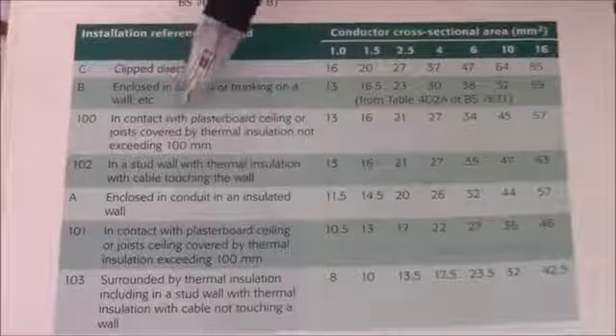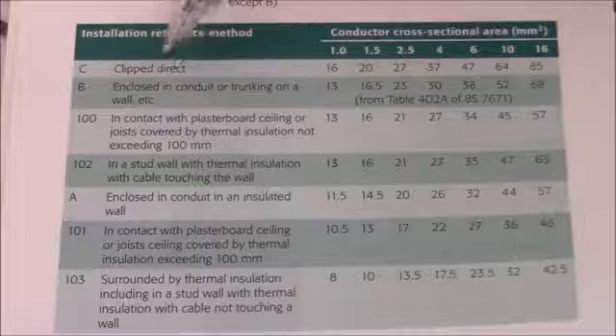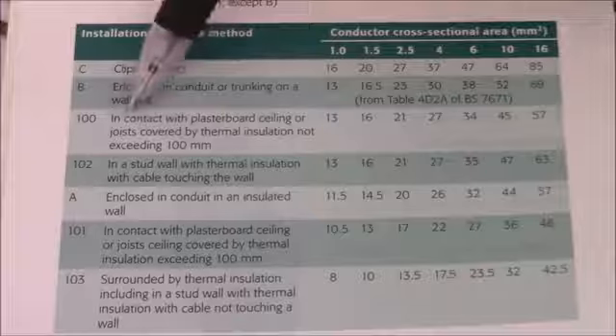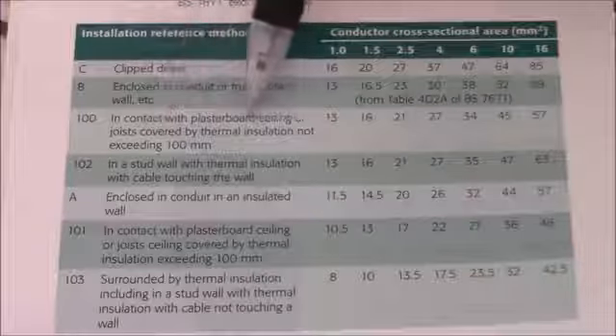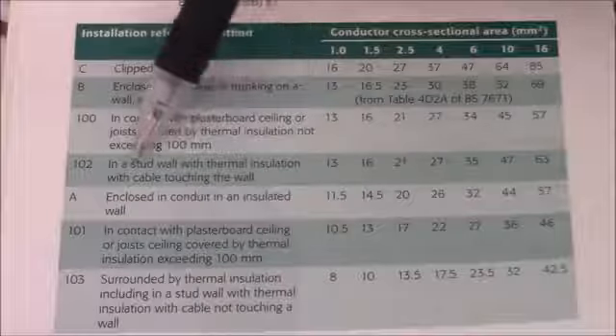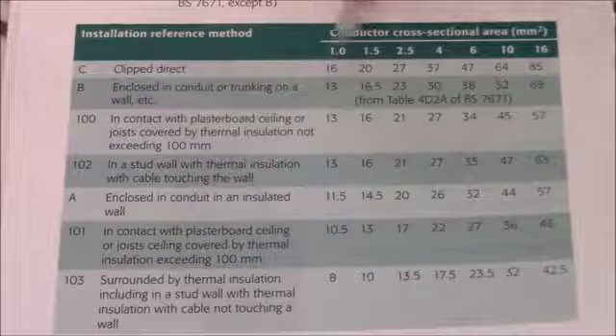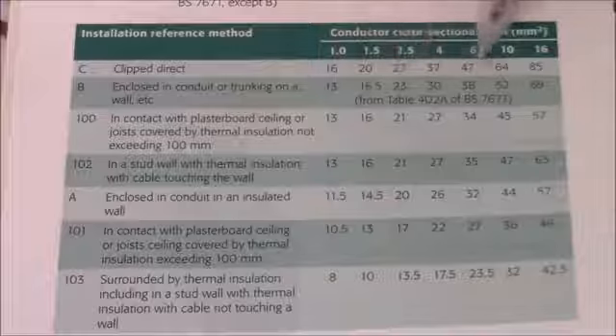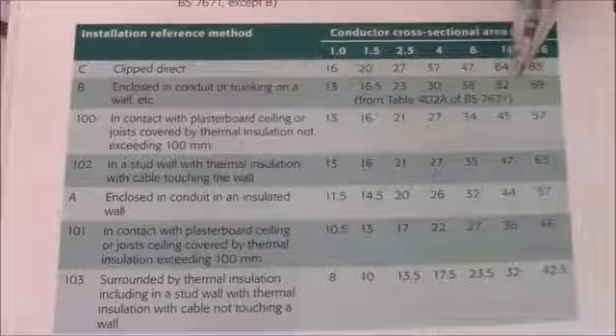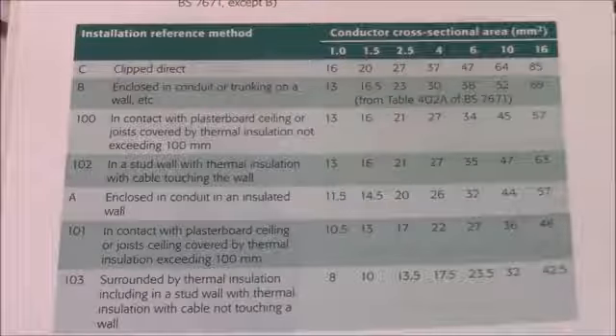The rest of the reference methods are just variations of the installation with insulation. So basically enclosing in conduit, trunking on wall, in contact with plasterboard, covered by thermal insulation not exceeding 100 mil, in a stud wall with thermal insulation, and so on. So when you clip direct the cable, the rating is very high. With any of the other methods in contact with insulation, the rating goes down. So it's a very useful book and a very useful table.